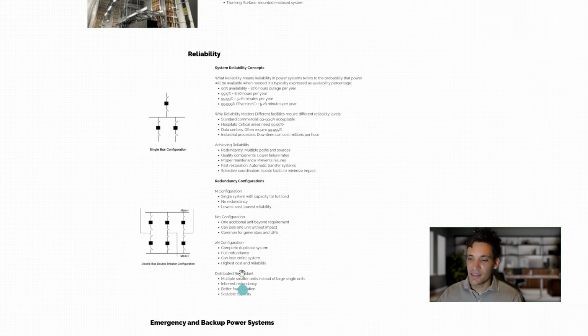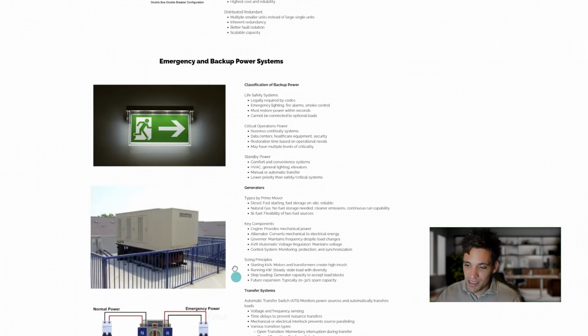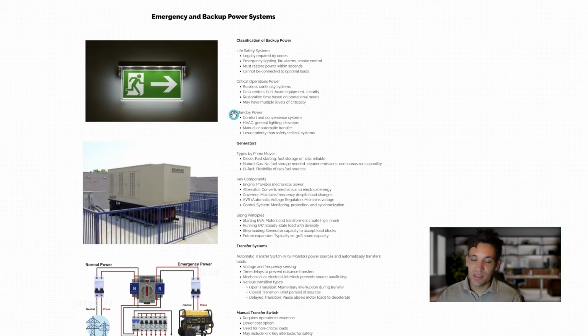In addition to just having secondary components everywhere, the other way we can increase the reliability of a system is with emergency and backup power. In practice, this means either having UPS battery backups or secondary generators. So if you lose the grid supply and the power drops out, the critical systems that you're powering have a secondary source of power. There are a couple of different classifications of backup power. There are life safety systems, where you're legally mandated by codes, standards, whatever, to have a battery backup. For example, in Australia, emergency lighting has to have its own independent battery backup, so if you lose the power, the emergency lights stay on.